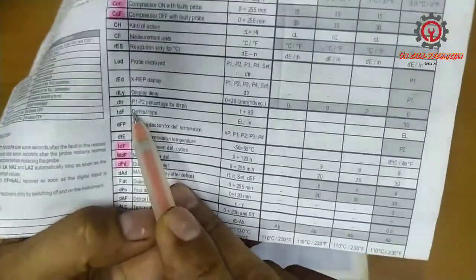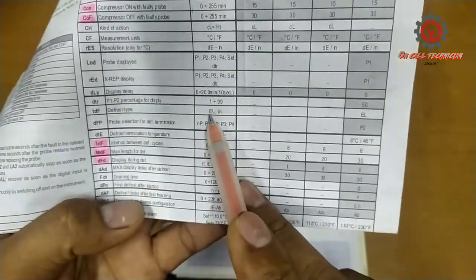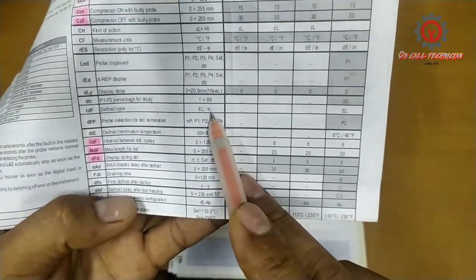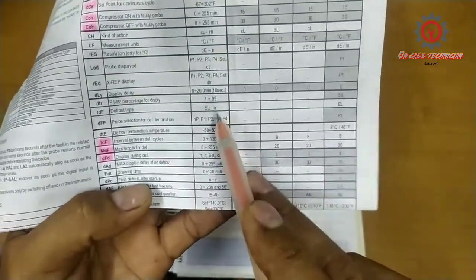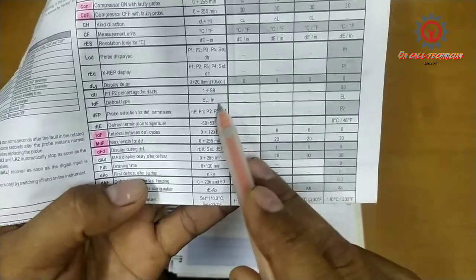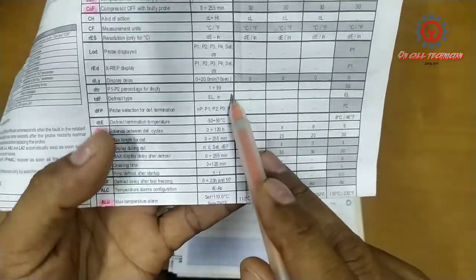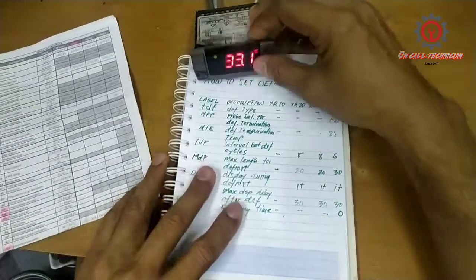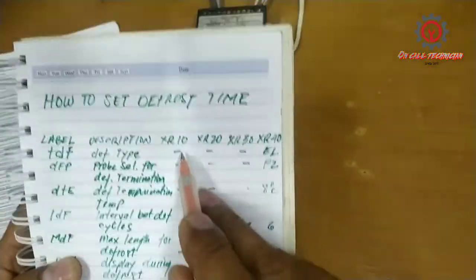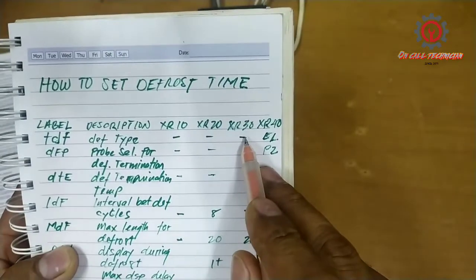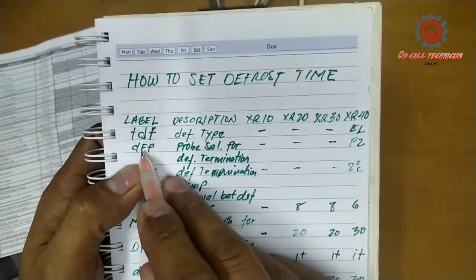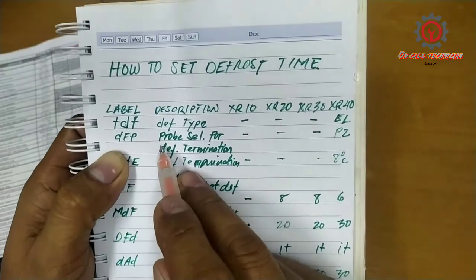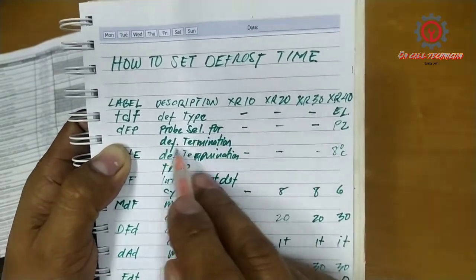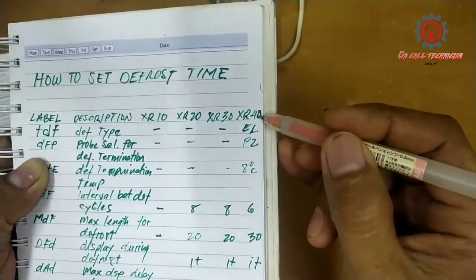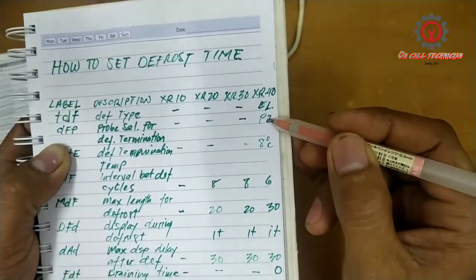Defrost type. Under the defrost type, we have electrical and in. And the default is the electrical. Okay? I'm going to make a separate tutorial about this. And we don't have this for the 10, 20, and 30. And next guys is the DFP. This is the probe selection for the defrost termination. In XR40CX, we have it set to P2.